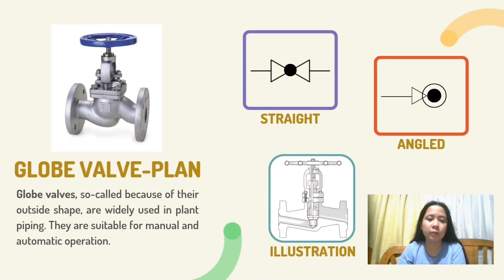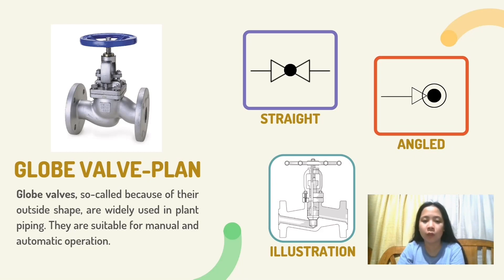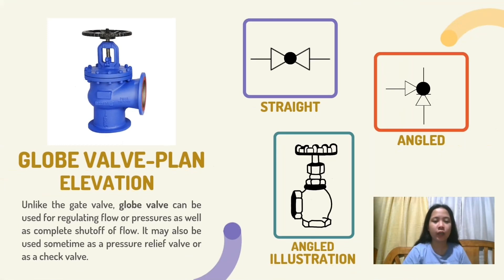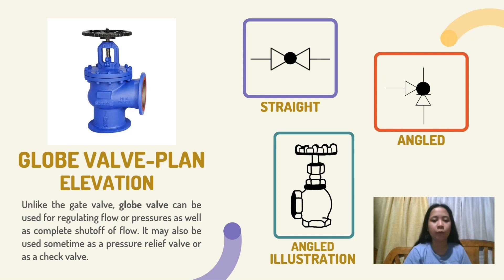Globe valve. Globe valves, so-called because of their outside shape, are widely used in plant piping. They are suitable for manual and automatic operation. Here are the symbols: straight and angled — the illustration of globe valve. Globe valve elevation: unlike the gate valve, a globe valve can be used for regulating flow or pressure as well as complete shut-off. It may also be used as a pressure relief valve or as a check valve. Here are the symbols: straight and angled illustration of globe valve elevation.